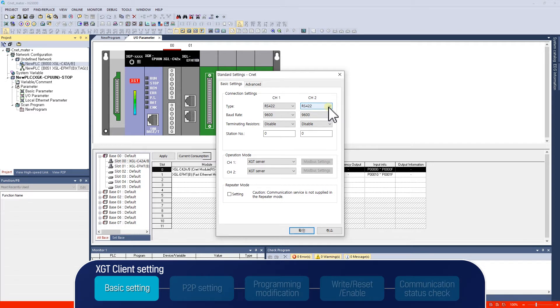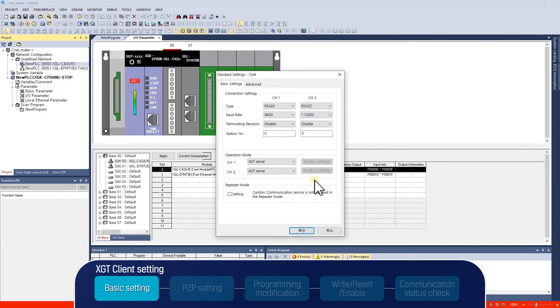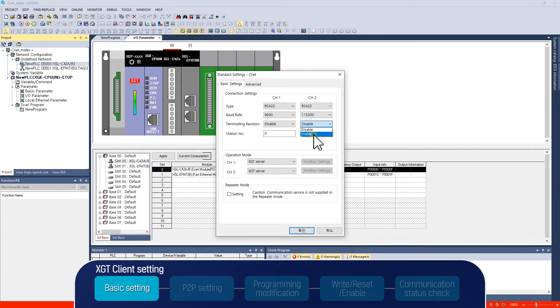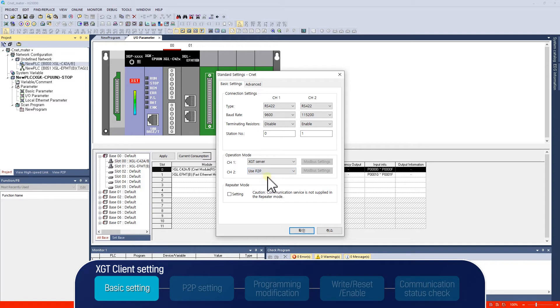In this example, channel 2 is used, so change the channel 2 communication parameters. It starts by changing the baud rate to 115,200 BPS and communication type to RS422. Since the master PLC is installed at the end, we will activate the terminating resistance and set the station number of the master PLC to 1. Operation mode is also important.